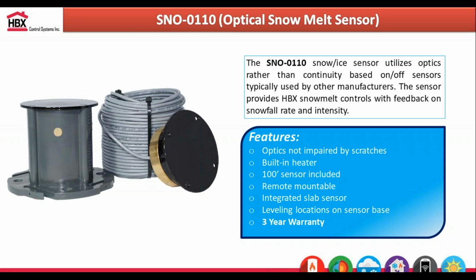So what really separates us from everyone else is this sensor that goes outside in the slab. Typically what you see in the market nowadays is a brass continuity sensor. Typically these are like Tekmar sensors, Caleffi, Roth has a metal continuity sensor, Heat Timer as well. But we use optics. What advantage that allows us is that we can actually see snowfall. So since we can see snowfall, we can turn on your system based on the snowfall rate intensity you want it to come on at.